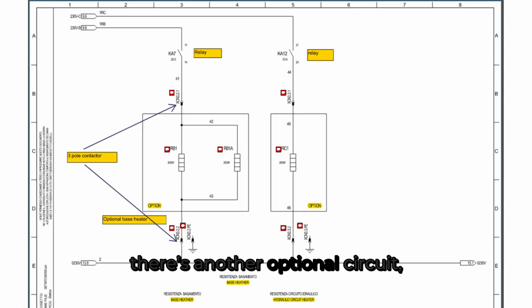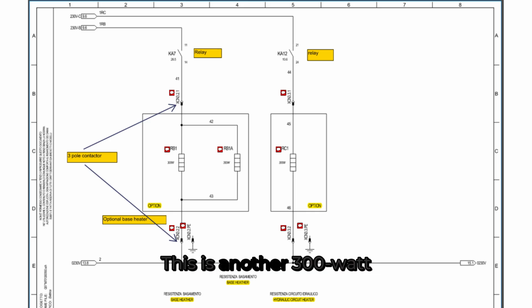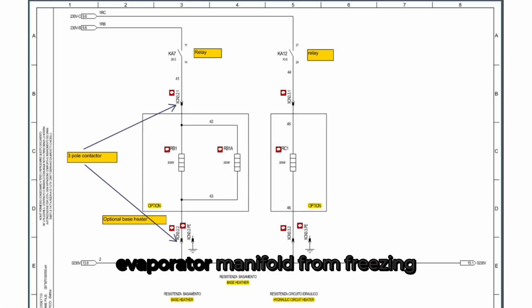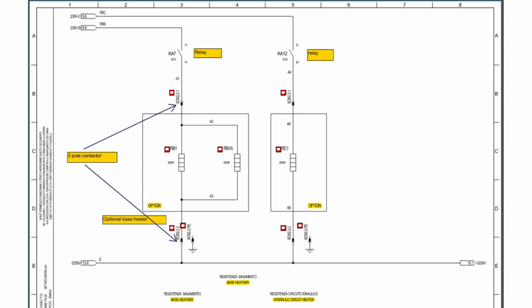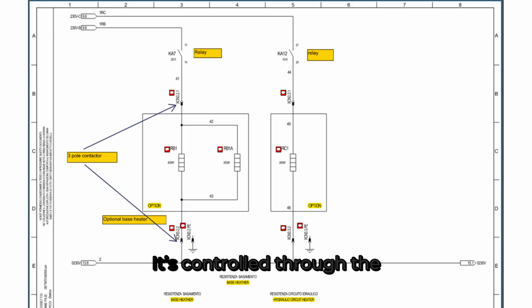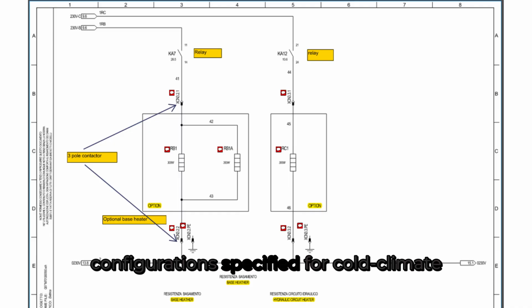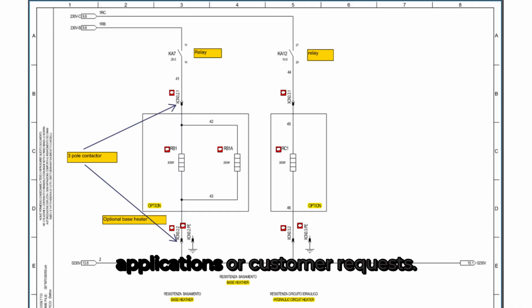There's another optional circuit, the evaporator or hydraulic circuit heater, labeled RC1. This is another 300-watt heater, designed to protect the hydronic piping or evaporator manifold from freezing when the unit is idle. It's controlled through the KA12 relay, which energizes the heater based on temperature conditions or system mode. Both circuits are marked as optional, meaning they are included only in configurations specified for cold climate applications or customer requests.